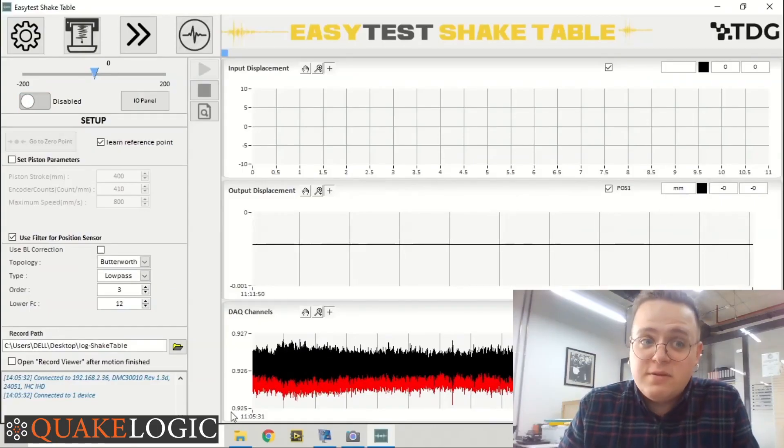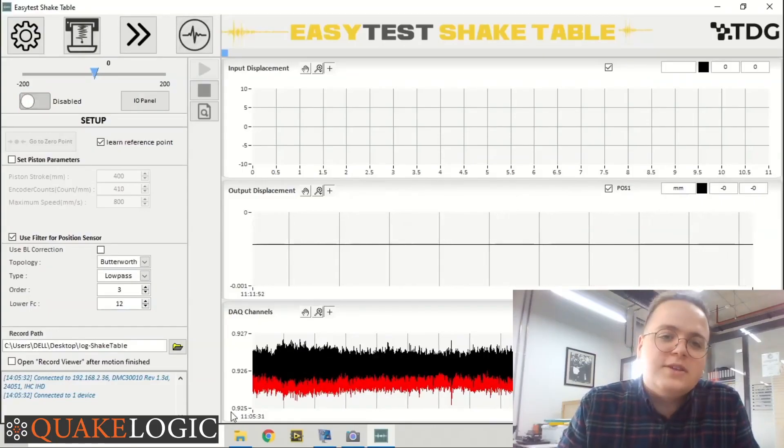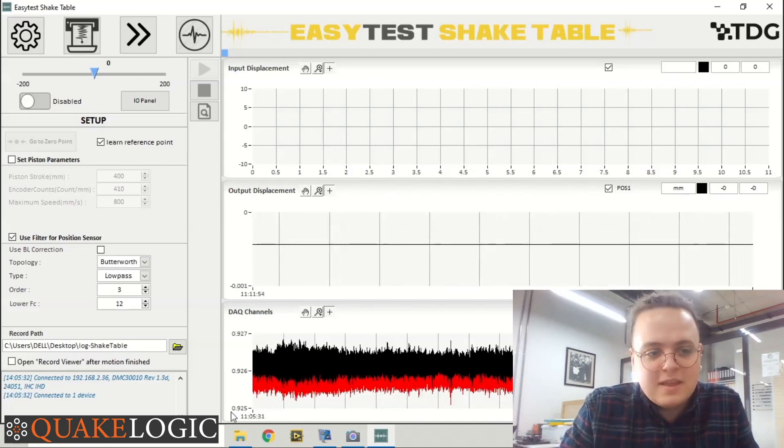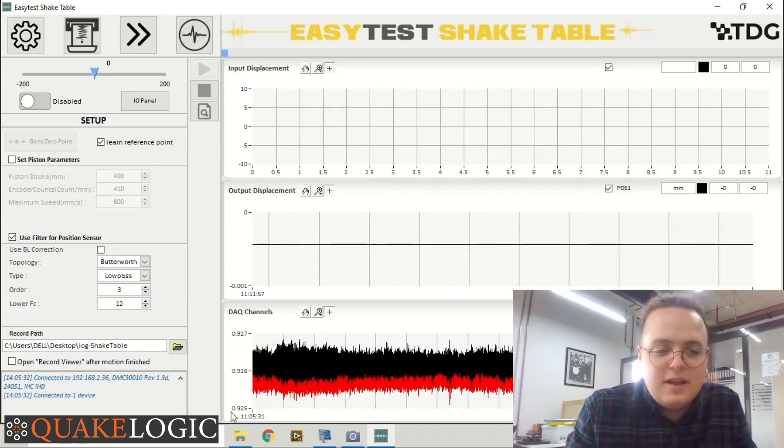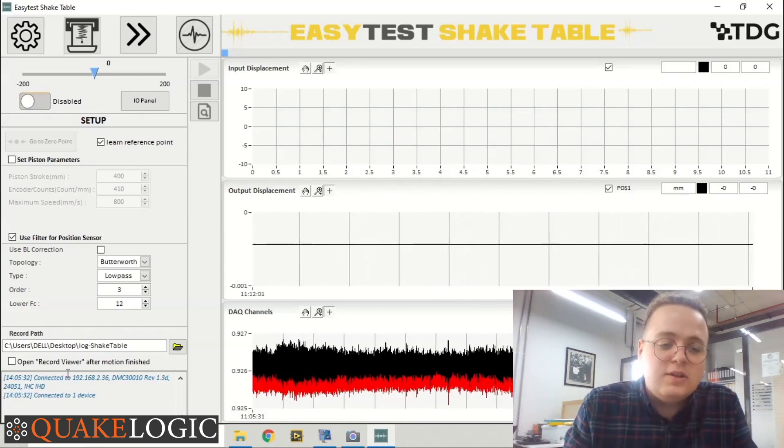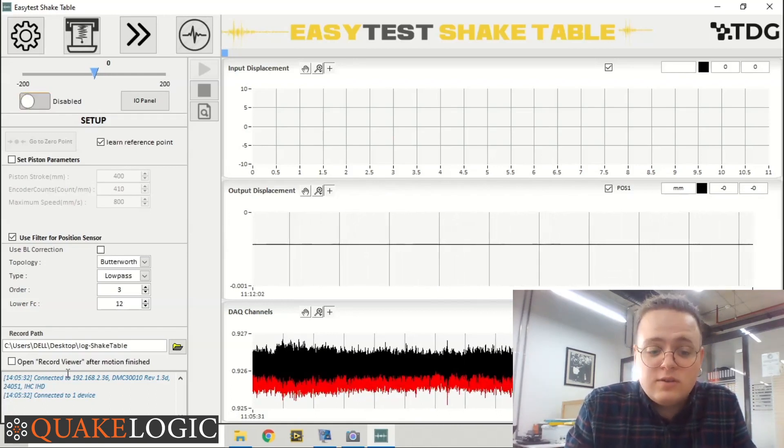Now let's talk about our software for this shake table. When we open up the software, the setup screen will appear on the left, and on the right we can see several graph displays. As can be seen from the bottom left with the blue color text, our software automatically connects to the shake table which is connected to our computer via Ethernet.